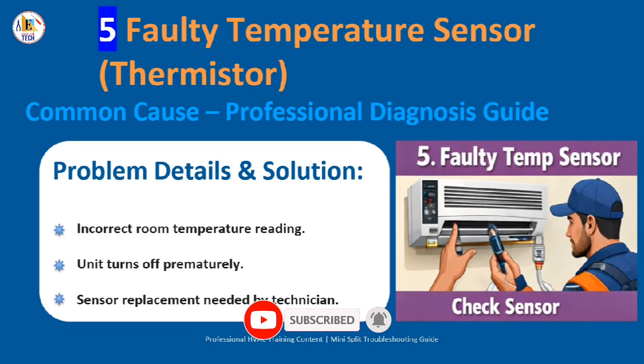5. Faulty temperature sensor, thermistor. What happens? The thermistor reads room temperature and tells the system when to stop. If faulty, it sends incorrect signals. What you notice? AC turns off too early. Room not reaching set temperature. Uneven cooling. Professional fix. Sensor testing and replacement by a technician.